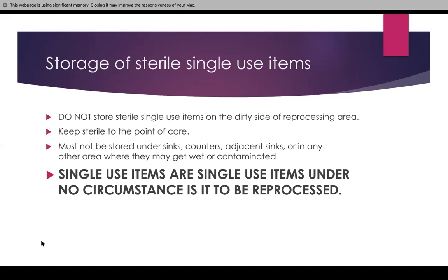For storage of sterile and single-use items, you cannot store them on the dirty side of the reprocessing area. The reprocessing area has to be a single flow — from dirty to the sterilization area to the sterile area. You cannot go from sterile to dirty — the whole concept is loss of sterilization. You have to keep items sterile to the point of care. You cannot store anything under sinks, counters, or adjacent to sinks because they can get wet or contaminated.